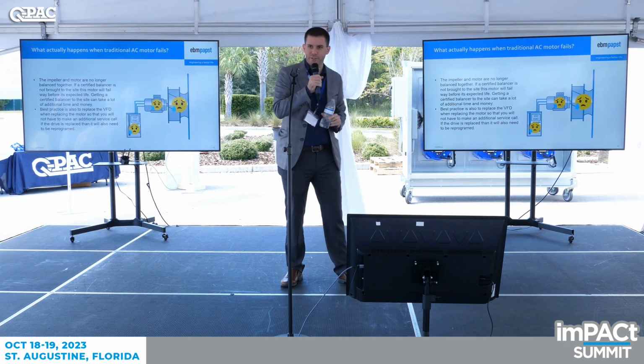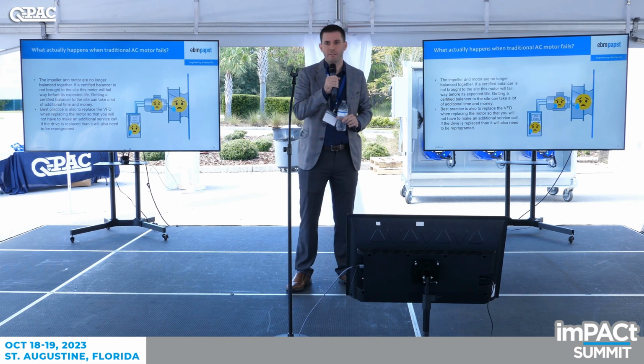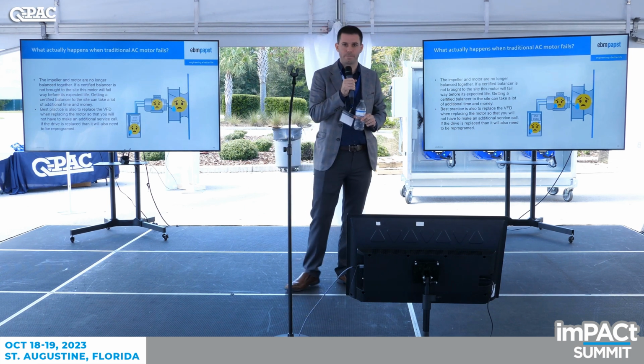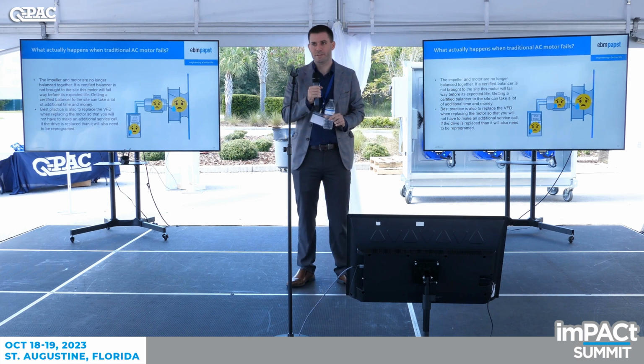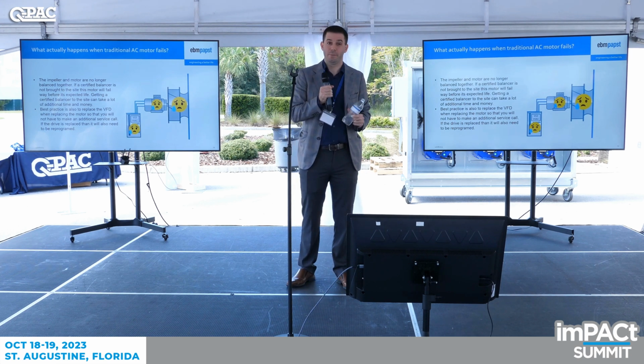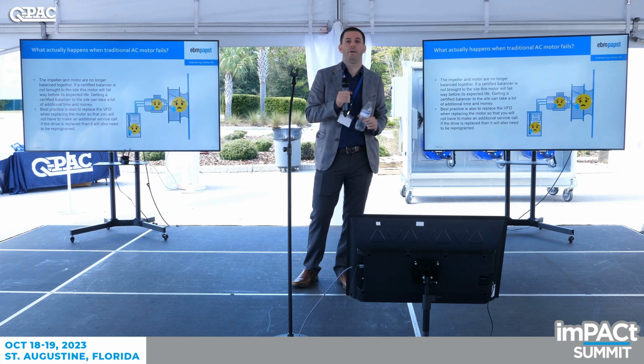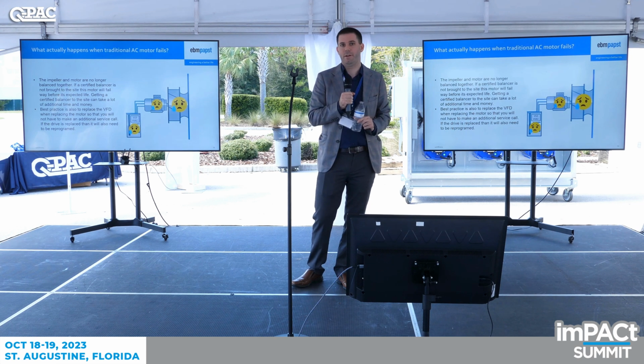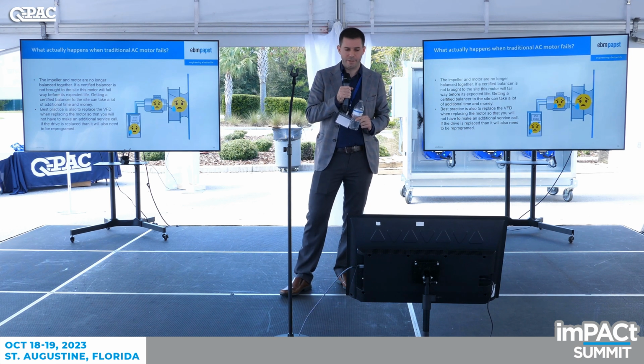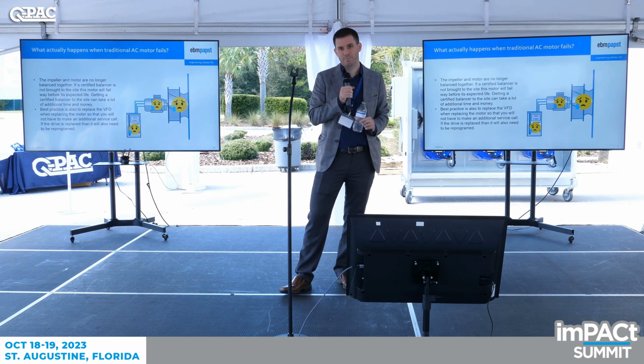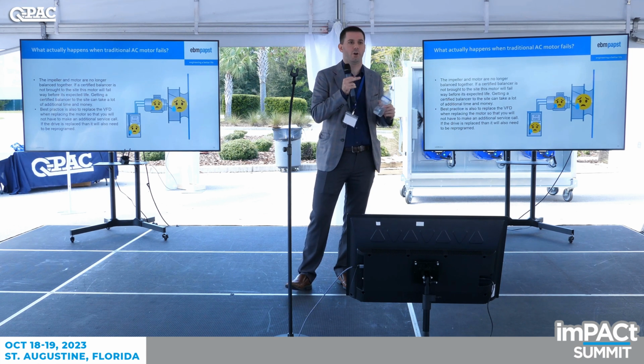Also, as I showed before, the VFD has a lifetime that's a little shorter than the motor. So when that first motor fails, the best practice lots of times would actually be to replace the VFD as well, because that way you don't want to make another service trip in another 2 months or however it is. So that's additional downtime, additional programming, additional cost.